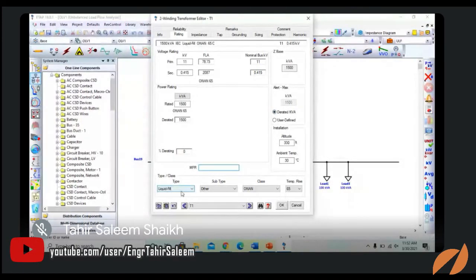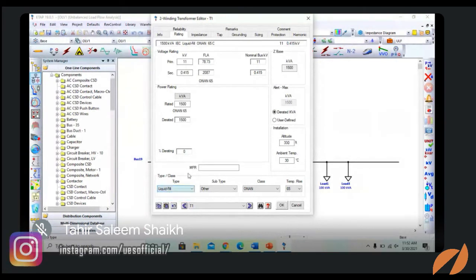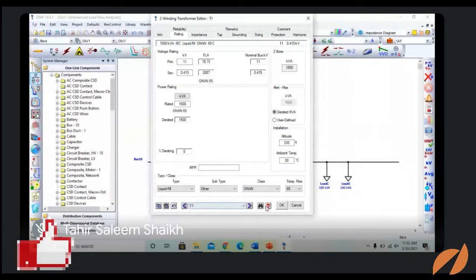Okay, so this is the liquid type, liquid filled or dry transformer. In many typical industrial or commercial power systems, we use the liquid filled, that is the oil filled transformer. What is the subtype? That is the mineral oil, or synthetic liquid with different ratings, including non-flammable synthetic liquid. So these are the liquid types which you are using.